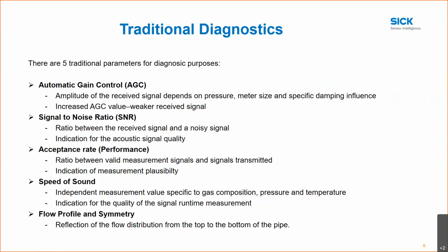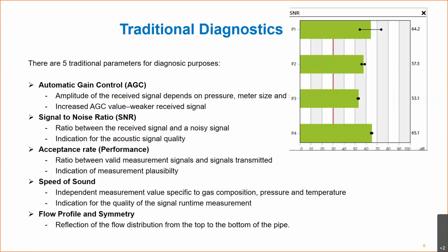Signal to noise is basically the ratio between the signal energy and the noise. It's an indication of good acoustic quality. In the signal to noise diagnostics, on the values page, you'll see where you have a certain ratio between the signal and noise. Anytime that gets below 30 decibels, you probably want to investigate what's causing that signal to noise ratio drop, which is usually an indication of some kind of interference or possibly some buildup in front of the transducers.